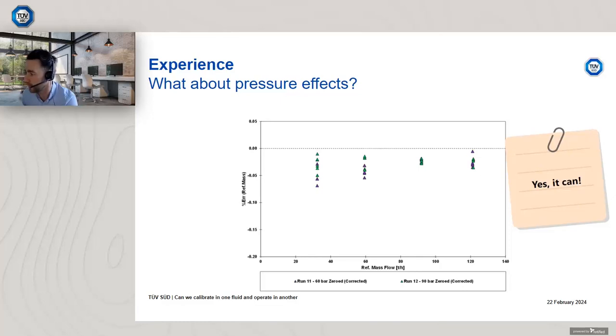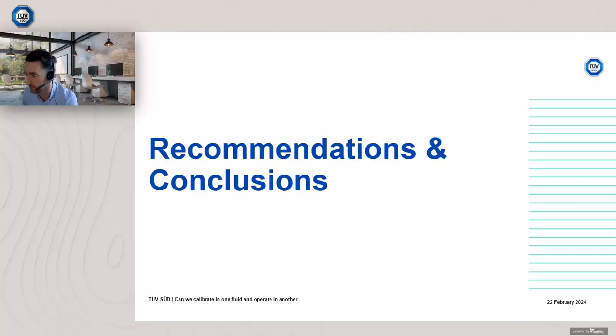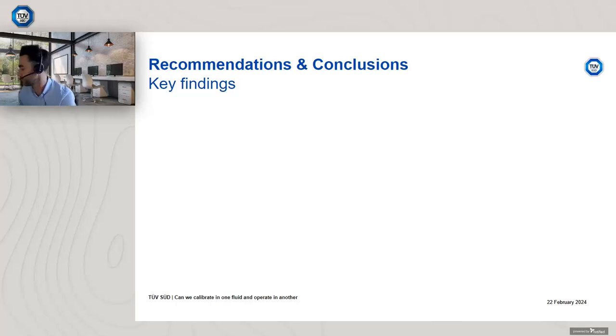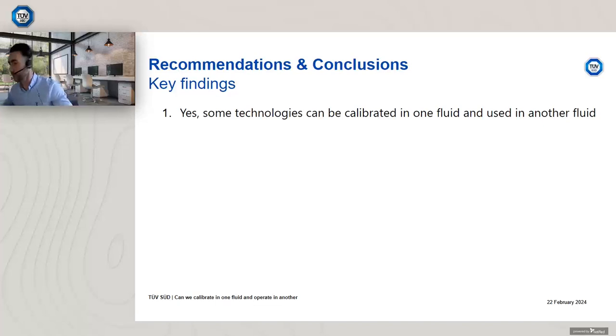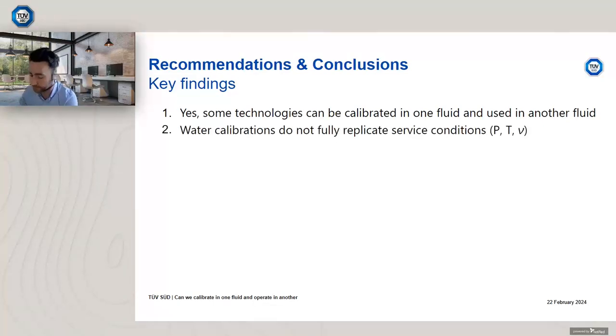So yes, it can be extrapolated with a known uncertainty. The uncertainty will be slightly increased because it's outside of the range at which you derive the correction. So what are the recommendations and conclusions? So going back to the question, the title of today's webinar, can we calibrate in one fluid and operate in another? Well, the key finding is yes, some technologies, not all, can be calibrated in one fluid and used in another. However, you have to be mindful of the measurement uncertainty.